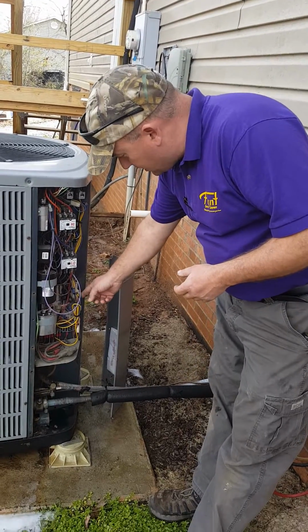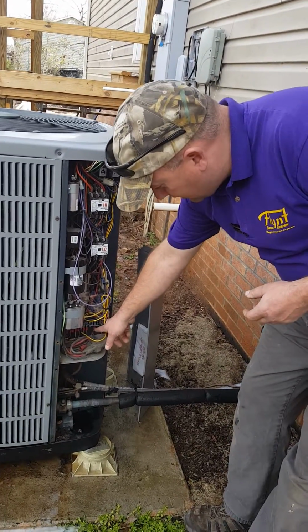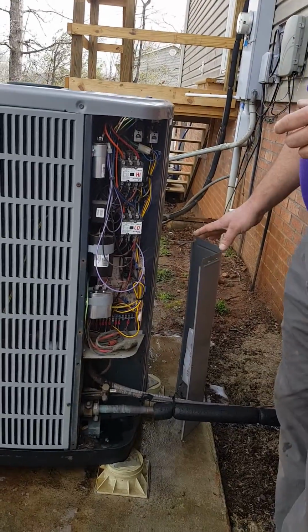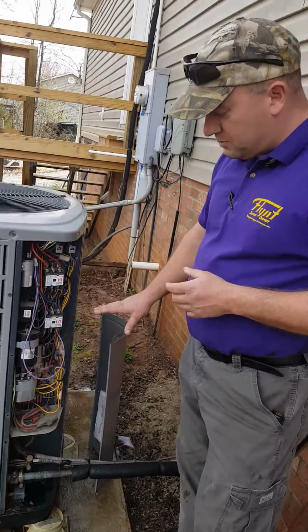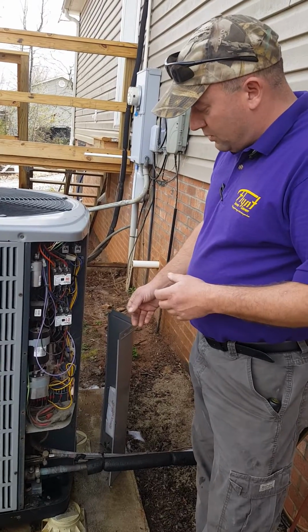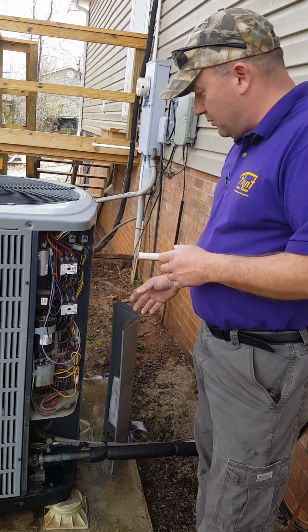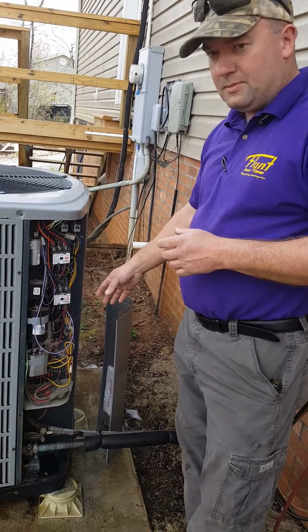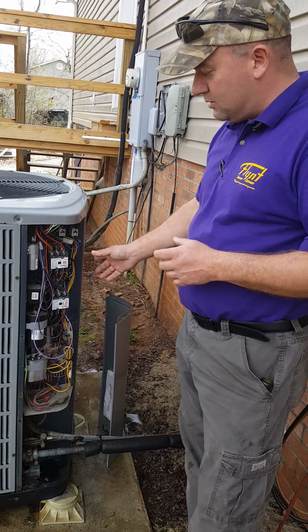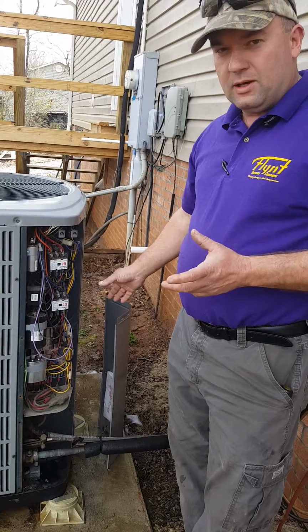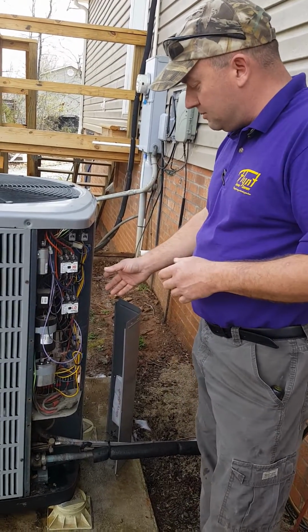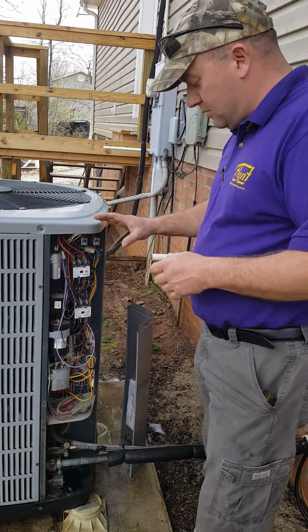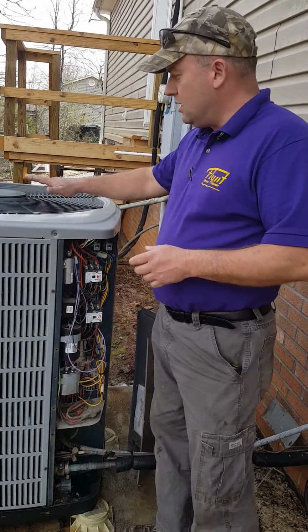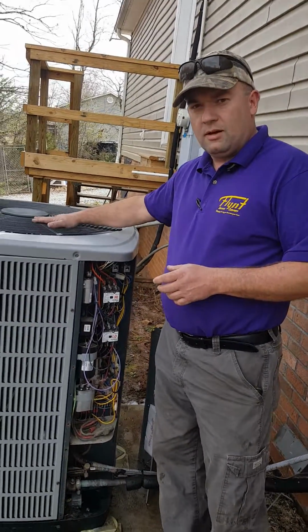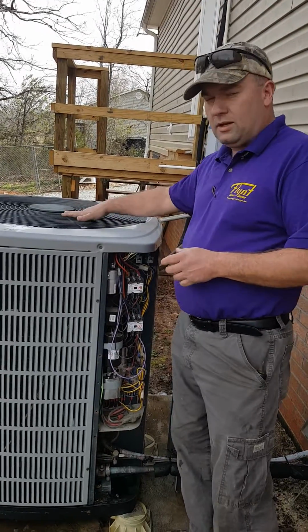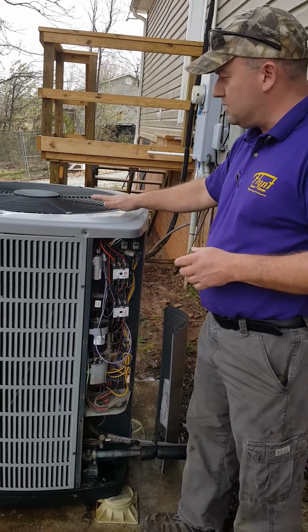Then on this unit we also have a control board. We have thermostat connections down on the bottom. We're going to check all those connections, making sure no wiring has been damaged, rubbed, or loose. We're also going to clean out spider webs and all the bugs that hibernate in these things through the winter time. Those spider webs can cause problems on the units. While we're cleaning the coils, we're also going to take the fan motor and fan top off this unit and clean out all the leaves and debris that build up in these things in the fall time.